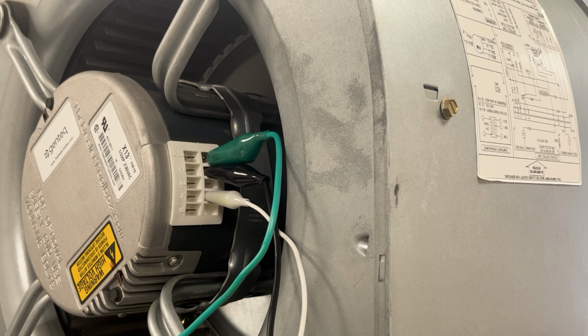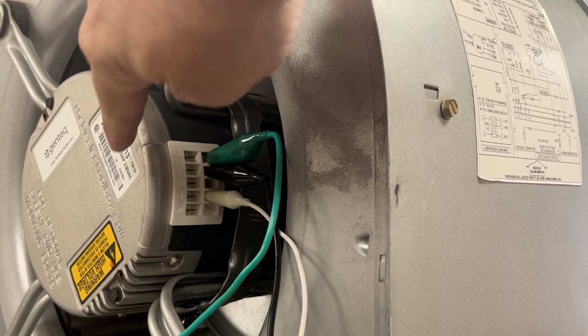But if you have one of those terminals that does not engage that motor, then what you can do for your customer to get them back up and running is run the one speed that is working, or for that 24 volt contact, and order a new module for it. Now, sometimes motors come with the modules, or you may have to have one that's programmed or whatnot. But at the end of it, I want to show you here, how do you test the motor itself? And there's a way to test this in the field by removing the back of the motor.